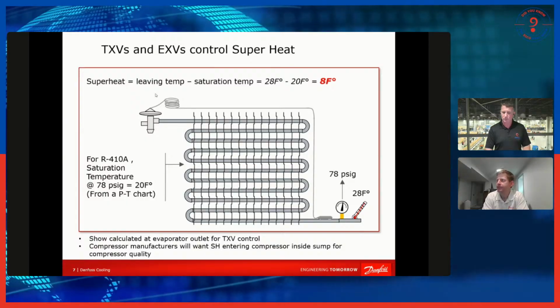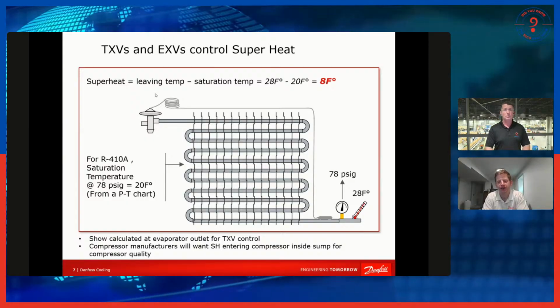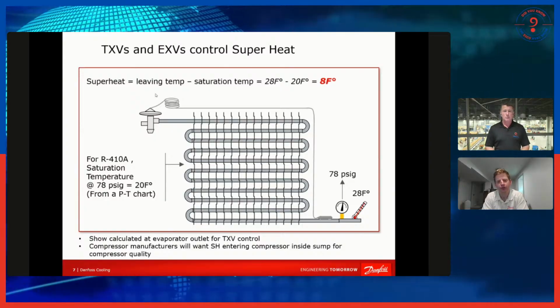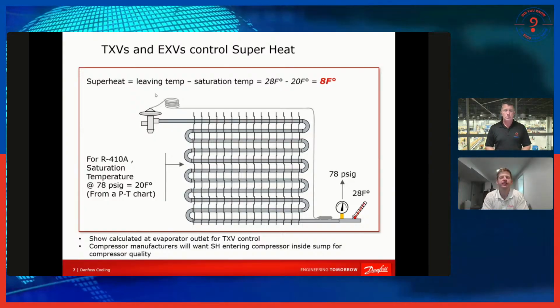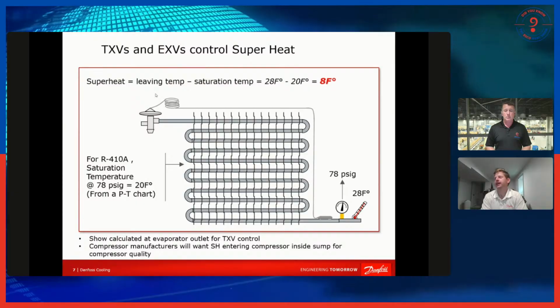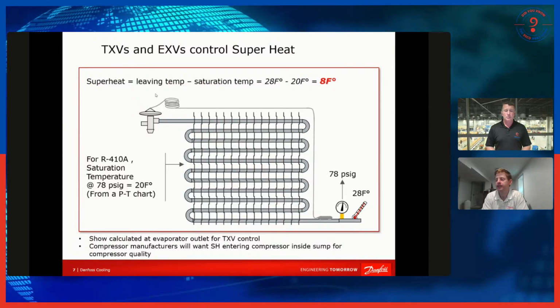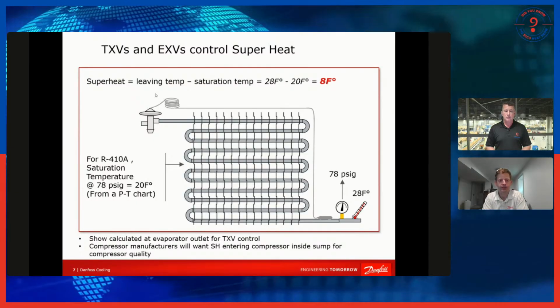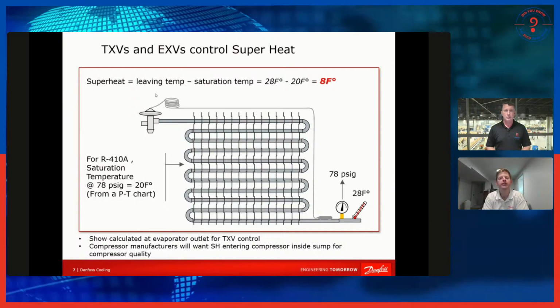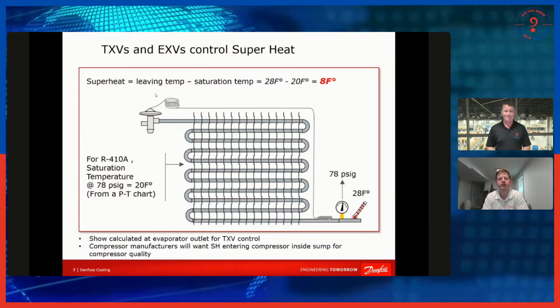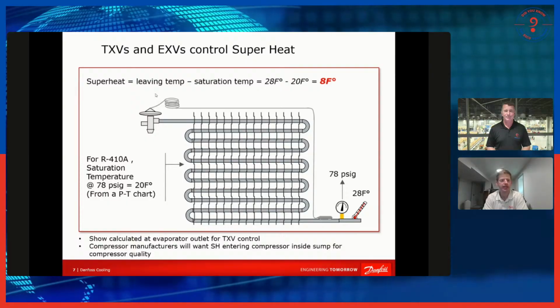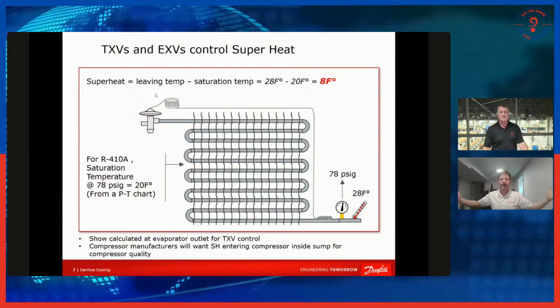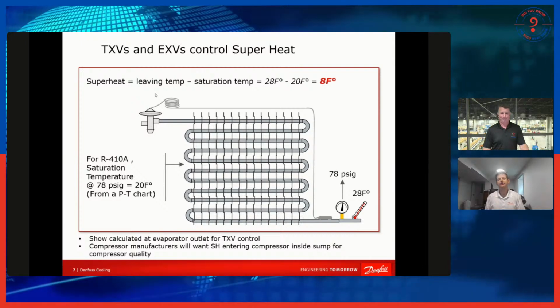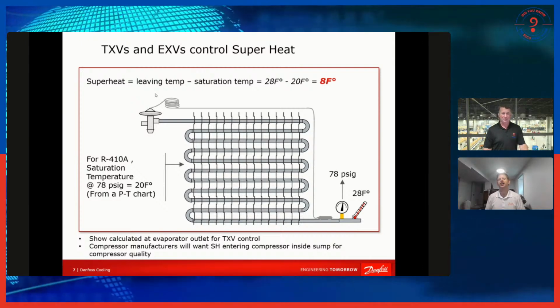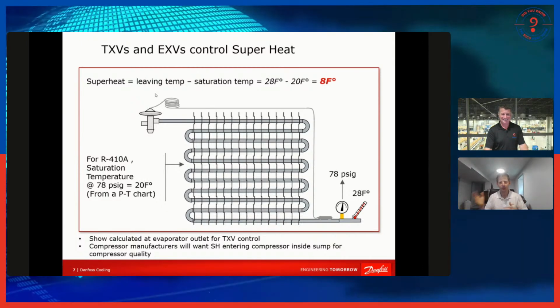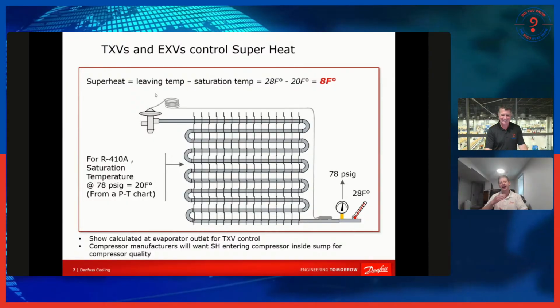So this is a simple slide. If you've gone through any sort of refrigeration or air conditioning training course, you've seen a slide like this, where it's just talking about measuring superheat. And it's very important to remember TXVs and EXVs, they're both superheat control devices. So if someone's telling you, oh, hey, I'm having a problem with the TXV or an EXV, first question I always ask them is, what's your superheat? And if someone can't give me an answer to that question, I always know, okay, let's go back to the draw. Let's take a few steps back.